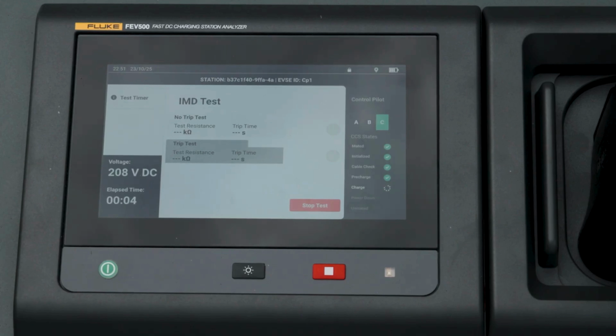Now we have the IMD test. So IMD stands for Insulation Monitoring Device. Similar to a GFCI that you would see on a level 2 station, this is also a protective device that's installed in the fast DC charging stations. I will call out a lot of the older infrastructure does not have an IMD, so if that's the case, you might see the trip test show up as a failure, which we're seeing in this instance.